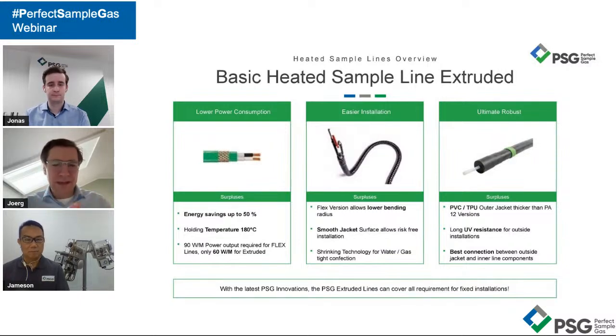It's really important to say: do not underestimate the heated sample line, and choose the right model. This is usually, by a factor of 20 or 30, the highest energy consuming item in your sampling system. It depends a lot on the length, but you usually have about 60 watts per meter, and just by calculating it roughly you can see how big this consumer is compared to the other two parts. So, as you're saying, don't underestimate it.